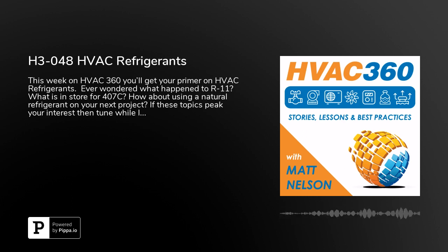With the 3-digit numbers, what about something like R11 or R22? The R11 or R12 means there's a 0 in front that is skipped. So the real number scheme would be R011 for R11 and R012 for R12, meaning they only have 1 carbon atom, but since we're subtracting 1, there would be a 0 in front. That 0 is typically skipped, but officially it is there.